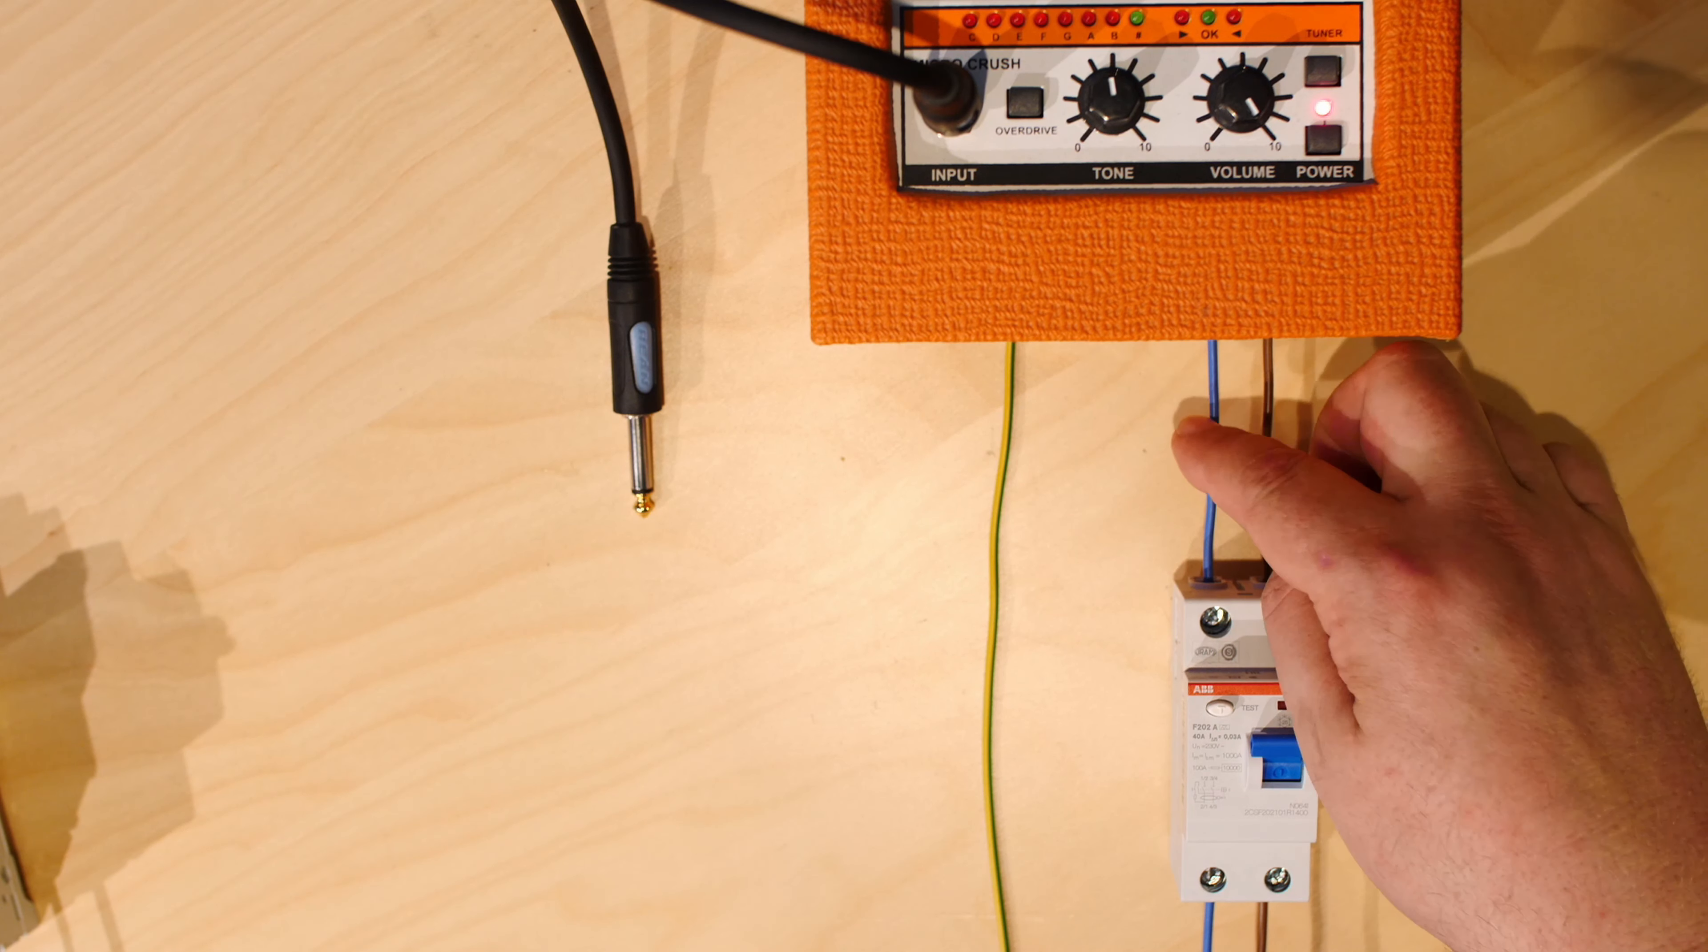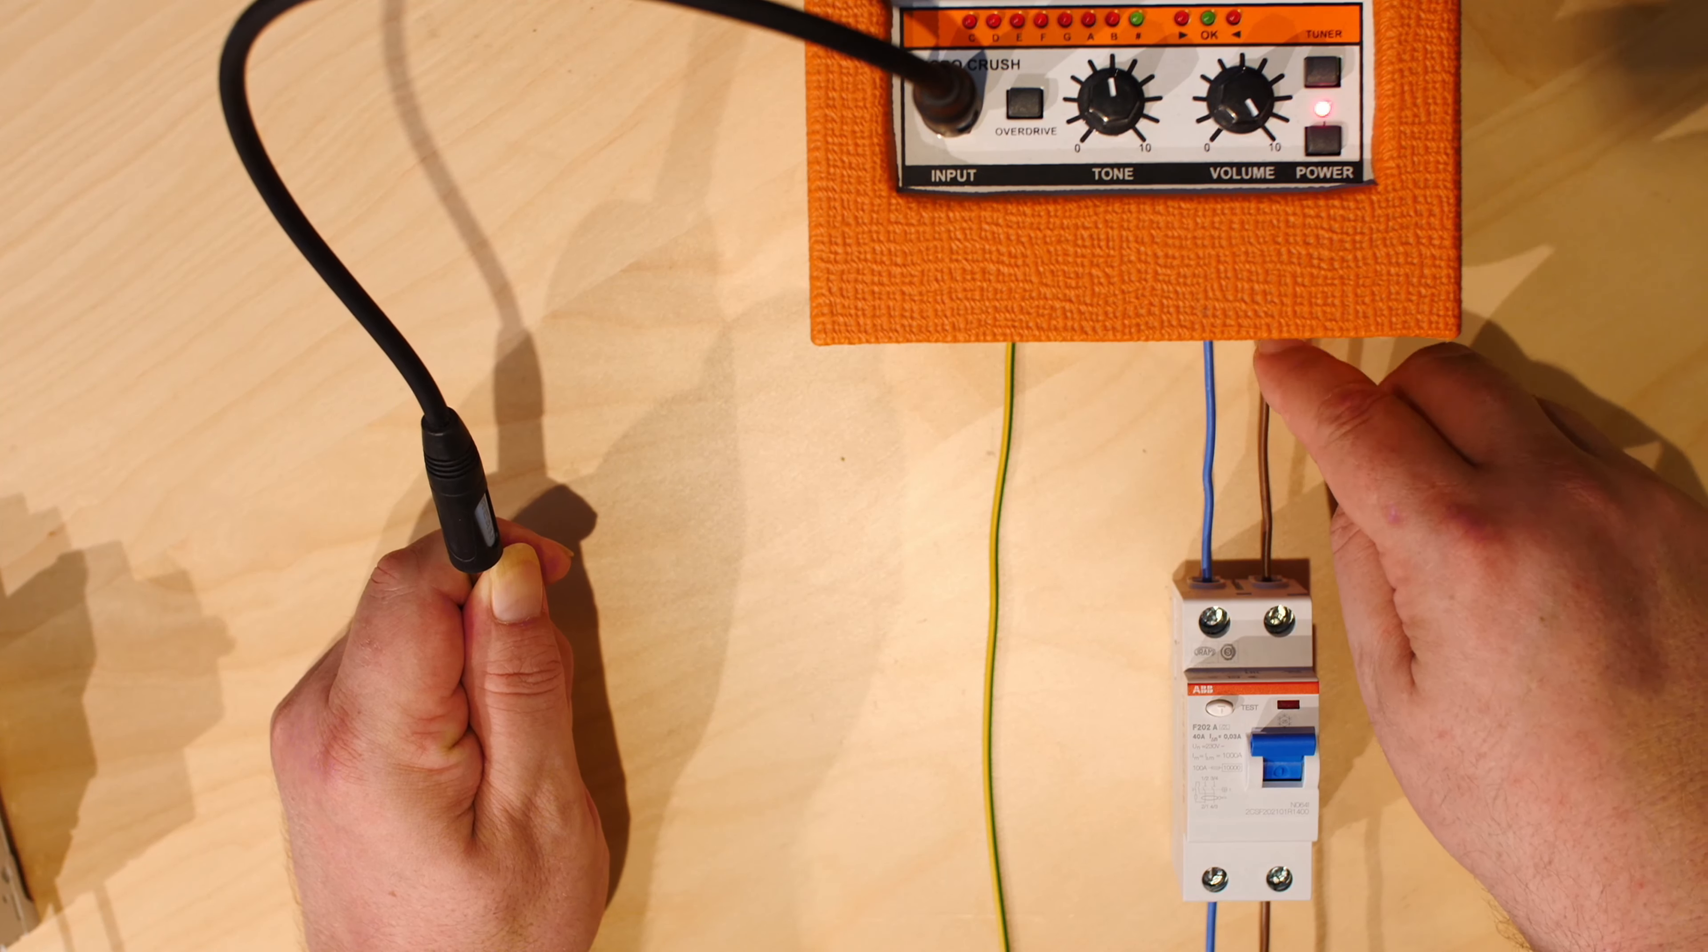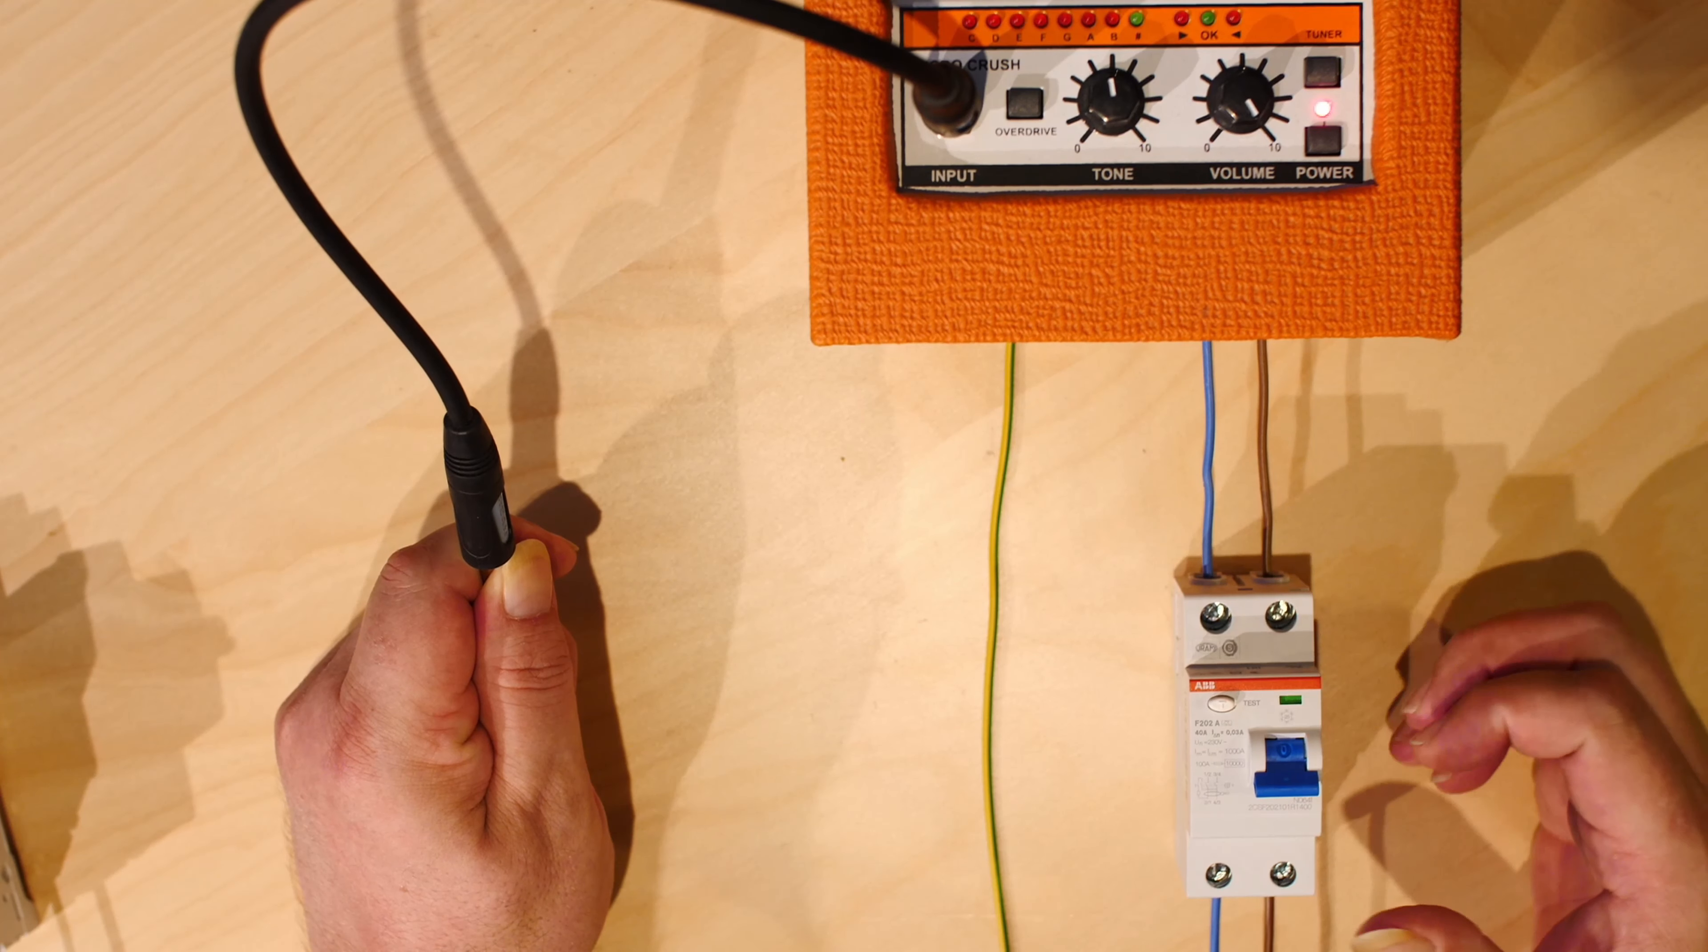But if for some reason, some of this voltage is going directly to ground, because I have an issue inside the amp, and some of the electricity goes through my body, then, for example, there will be two ampere flowing into the amp, but on this blue wire, only 1.9 amp are coming back, because the other 0.1 amp go through my body. And this difference, this device will detect the difference, and if they are not the same, it will, bam, switch off.